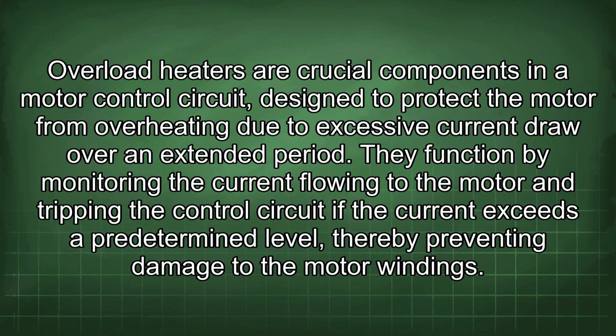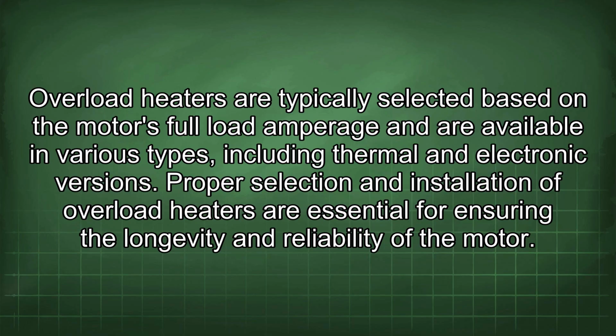Overload heaters are crucial components in a motor control circuit designed to protect the motor from overheating due to excessive current draw over an extended period. They function by monitoring the current flowing to the motor and tripping the control circuit if the current exceeds a predetermined level, thereby preventing damage to the motor windings. Overload heaters are typically selected based on the motor's full load amperage and are available in various types, including thermal and electronic versions.